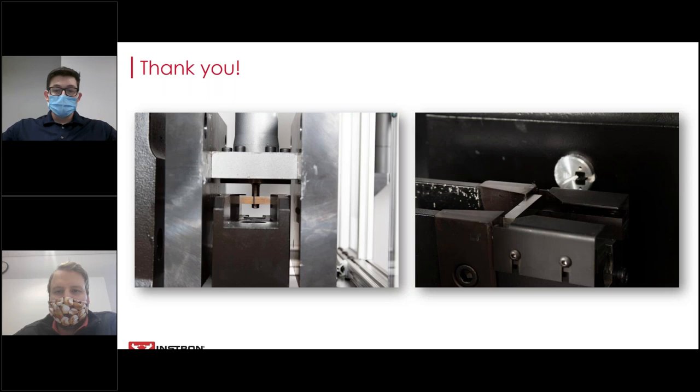Yeah, thanks for that. That's a good question. A lot of older impact testers are mounted to the floor. It's totally fine. You can pass all these standards if you mount your system to the floor. But again, you deal with the challenge of being non-ergonomic, and a lot of people want to raise that up. If that's the case, the requirement to meet these standards is that you want your foundation to be 40 times your hammer weight. Then you can work with your provider to talk about those details and how to get that mounted. But it's very common to mount your system up on a mounting block.